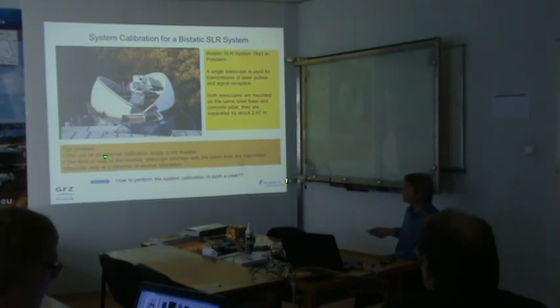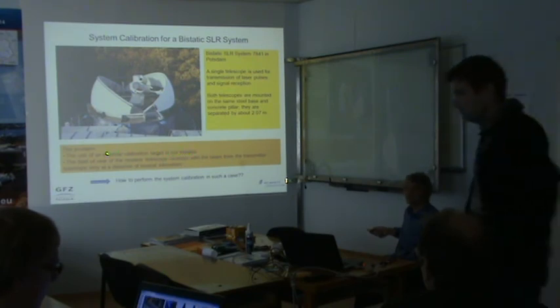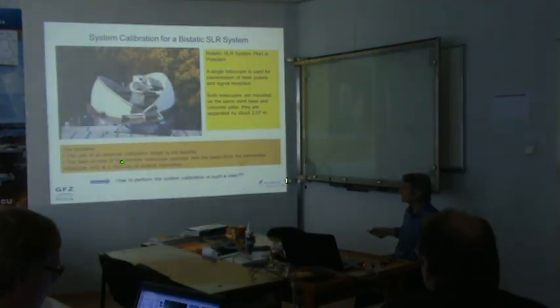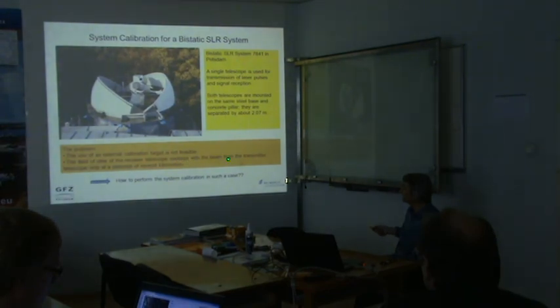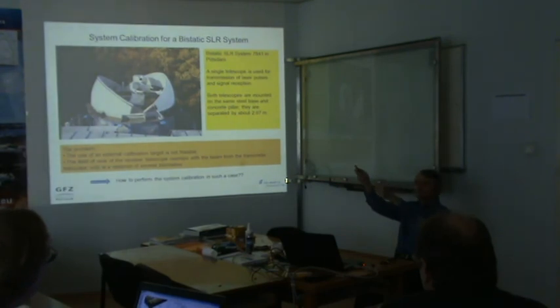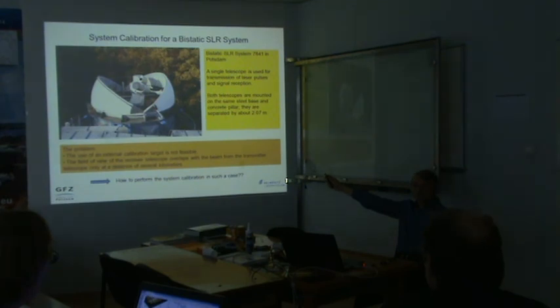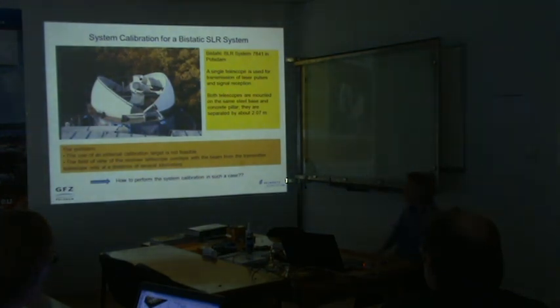You cannot use an external target. It's not feasible. In case you would like to use an external target, you would have to take into account that the field of view of the receiver telescope overlaps with the beam from the transmitter only at a distance of several kilometers. I have made a computation in mind, and it should be about 8 to 10 kilometers before the receiver telescope sees the beam from the transmitter, though they are only 2 meters apart. This is because of the narrow fields of view. So you are lost with an external target, and you can only use an internal or short-range target.